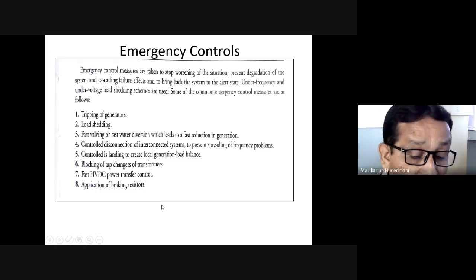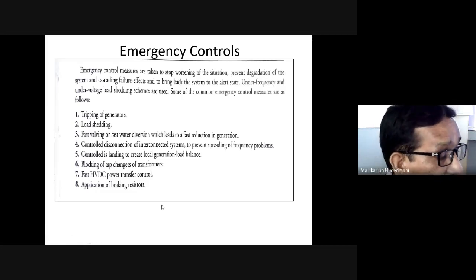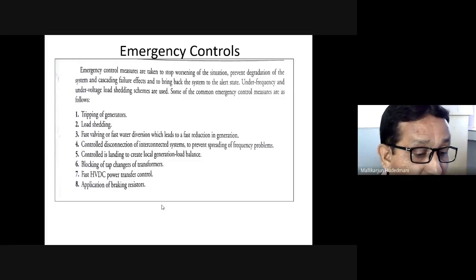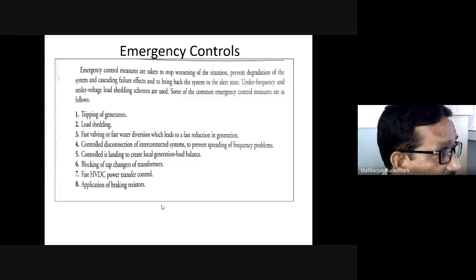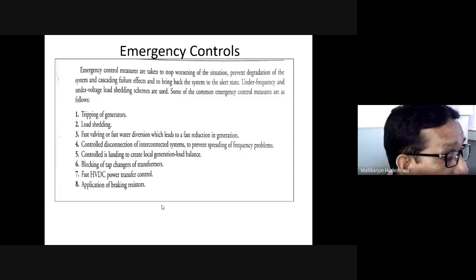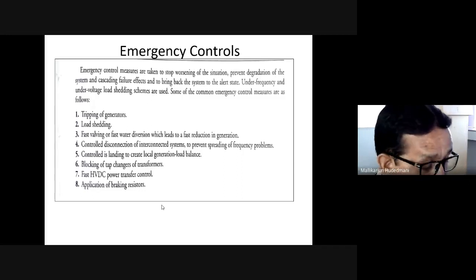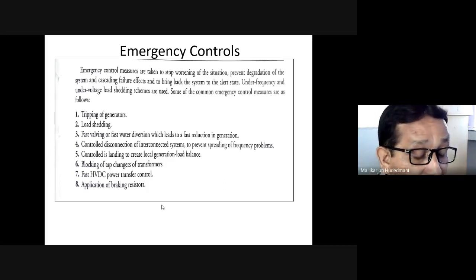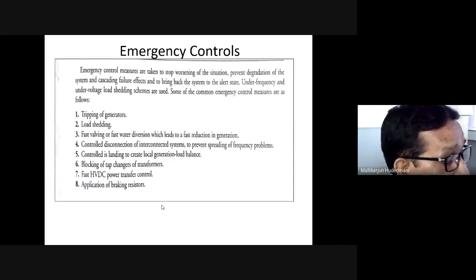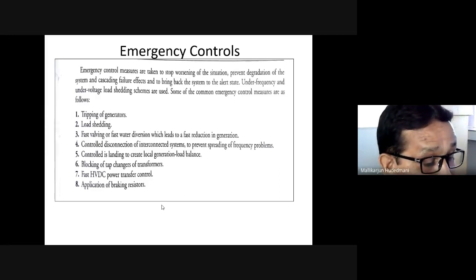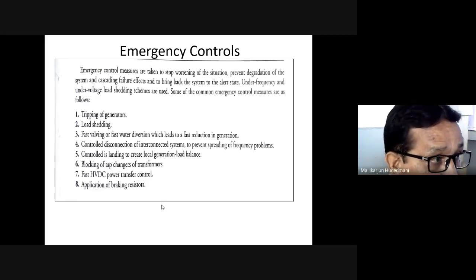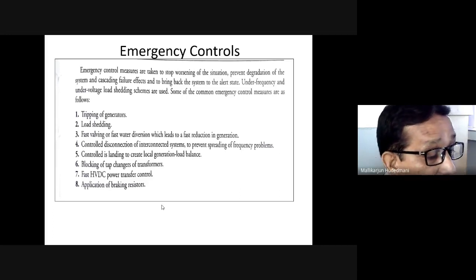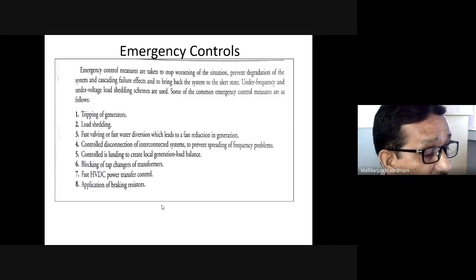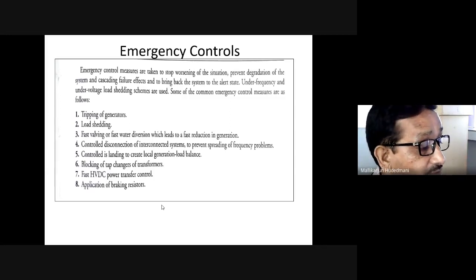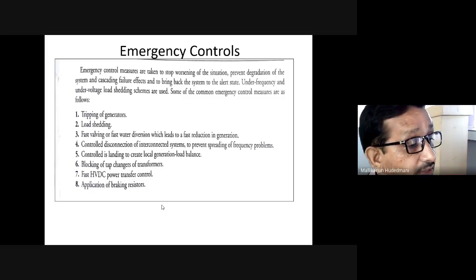These braking resistors are the large resistors kept in the generating stations or generating area, as and when the generator needs to be stopped, braked, and reduced to lower generation and stop it. At that time, the massive generation the generator has taken up, or the acceleration that the generator and the turbine have picked up due to the automatic controlling around that generation setup, has made the generator run at runaway speed, which is a very dangerous phenomenon. We call it a flyaway.